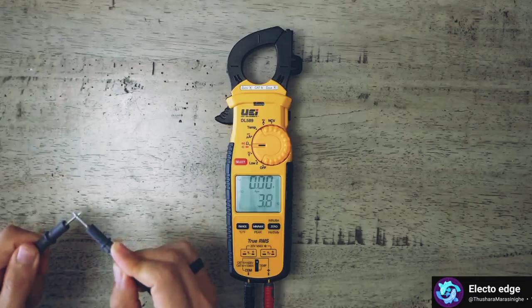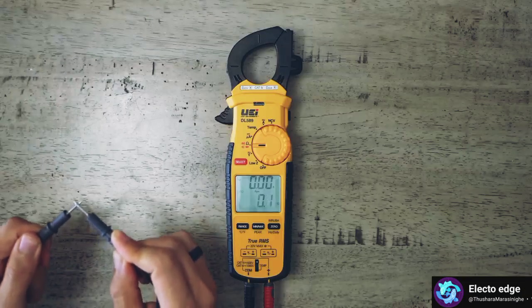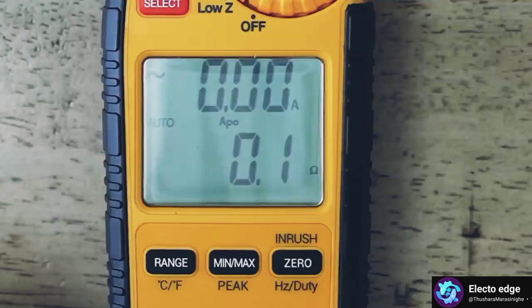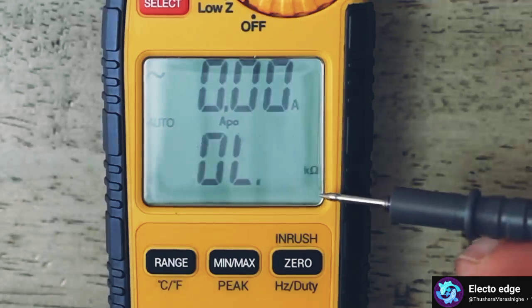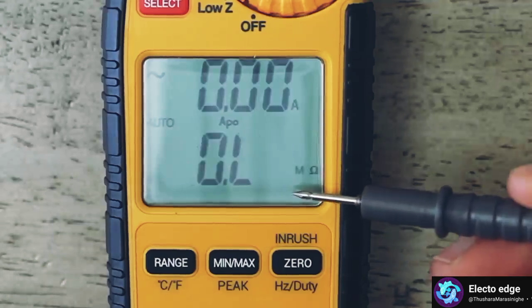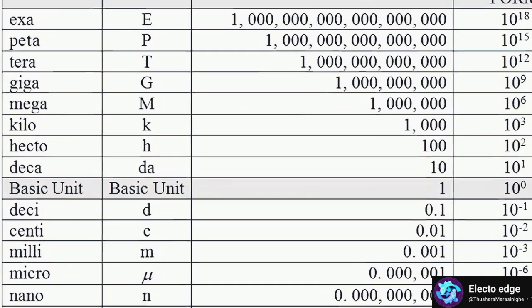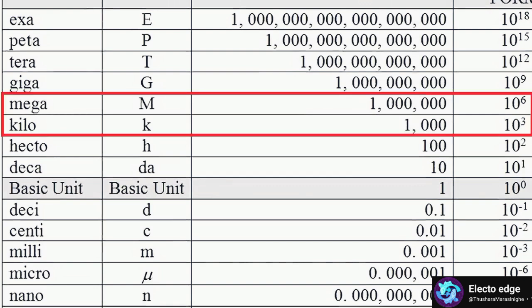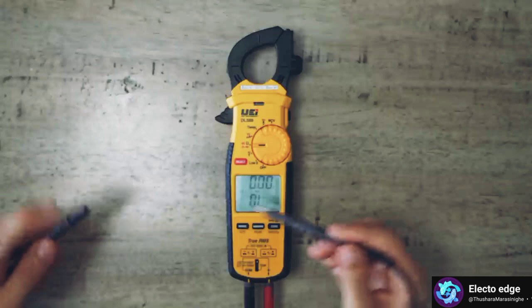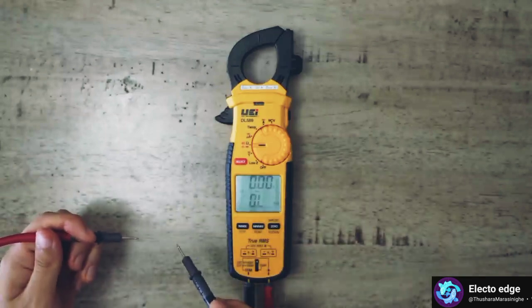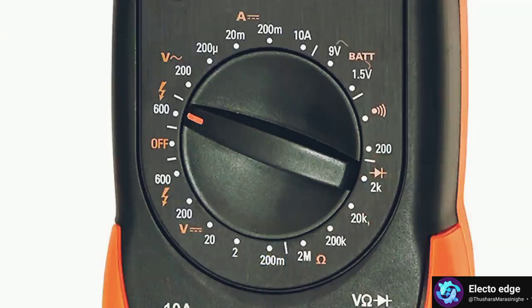The meter that I'm using is auto ranging, but when I let go of my leads, if you look at the symbol right here, notice how a K appears and an M appears. That stands for kilo and mega. My meter automatically ranges and it selects the proper range that I need whenever I put my leads on something to check resistance, but some of the cheaper meters, you have to select that range yourself.